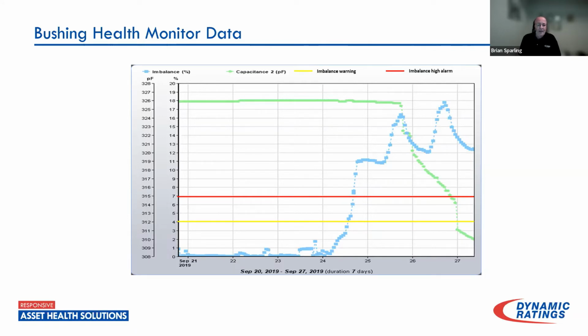The yellow line and the red line are the alarm limits. In other words, the yellow line is the first alarm, and the red line is for the second alarm, meaning get out there quickly before this thing shatters. So it was an interesting case where we detected a leak in the bushing, and this is how the data shows. But you can see that it happened over a relatively short period of time, where periodic offline testing of a bushing or even inspection of a transformer may not have been enough to capture this failing condition on that bushing. So a bad bushing failure of a transformer was averted.